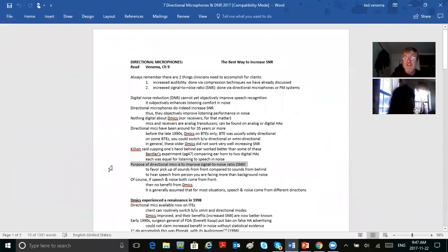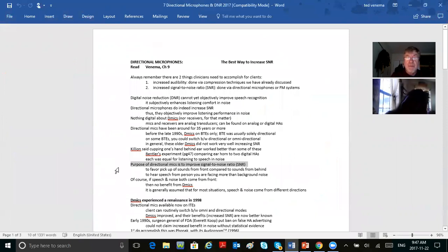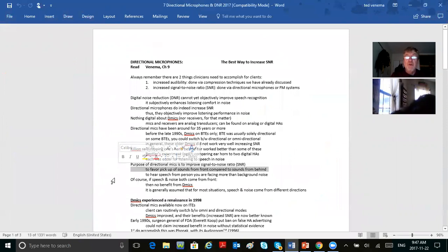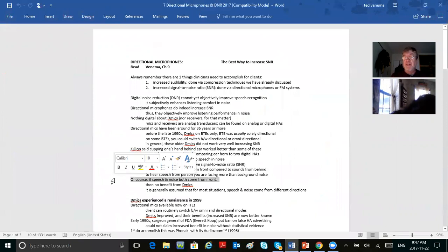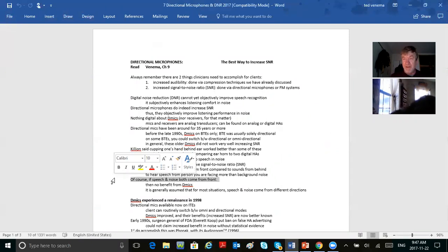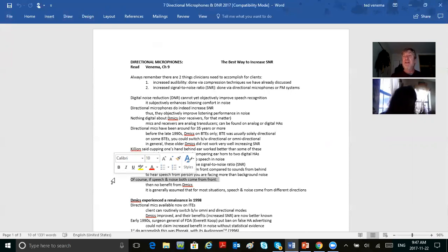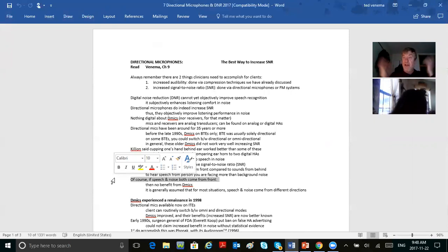The purpose of D-mics is to pick up the signal-to-noise ratio and improve it, to favor the pickup of sounds from the front compared to sounds behind. Put a star by this: if the speech and noise both come from the front, a directional mic isn't going to be of any help at all. D-mics are of biggest help if the sound of interest is coming from the front and the background noise is coming from other directions.